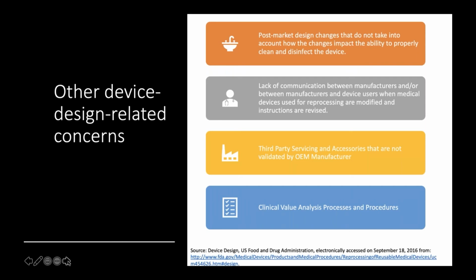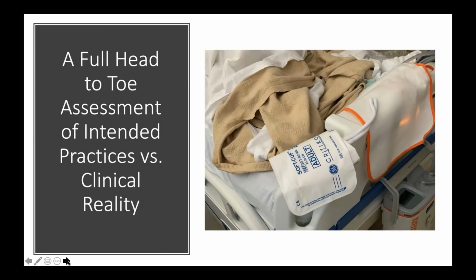That's one thing that stuck out with me over the years with outbreak investigations: healthcare facilities would have an outbreak and it would be associated with a loaner from the manufacturer. And they would have absolutely no clue of the history of that loaner, where it came from, the last time it was serviced, how often it's been disinfected, whether there have been any other issues with it, because it was not their device. And so there are all these different issues that might creep up with this.